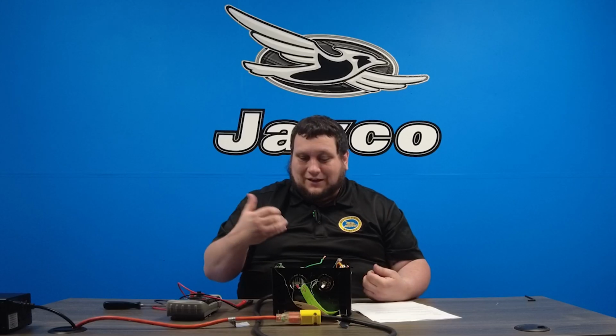Most electrical problems, especially in the RV world, can be boiled down to one of two things: either a tripped breaker or a bad connection. And these transfer switches not only detect on the feed side of the transfer switch, they also detect on the output side. So if we test good here, but we're not outputting good voltage or correct voltage here, we may have a connection problem that is not allowing enough voltage to pass through, and the transfer switch is not going to let it pass. So we always want to verify, do we have correct power coming to the device? And are our connections tight, clean, and ready to go?